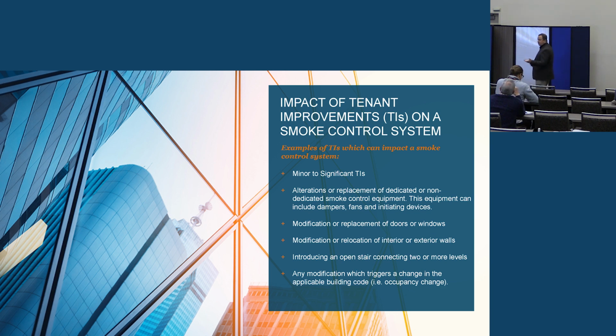Modifications to doors and windows. Like if I have a large atrium system or a sandwich pressurization system, remember those windows that were on a louver that automatically opened with an actuator, and you're like, why is there an actuator on this building? It was probably automatic, and it was probably makeup air for your smoke control. If you have power doors in the lobbies, they can be part of the system where the system goes into smoke exhaust from the atrium and all the doors in the lobby automatically open.